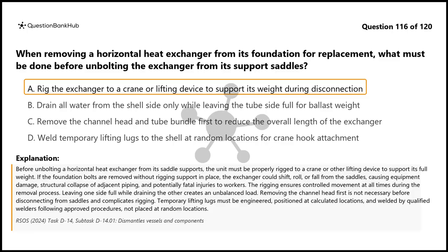Leaving one side full while draining the other creates an unbalanced load. Removing the channel head first is not necessary before disconnecting from saddles and complicates rigging. Temporary lifting lugs must be engineered, positioned at calculated locations, and welded by qualified welders following approved procedures, not placed at random locations.